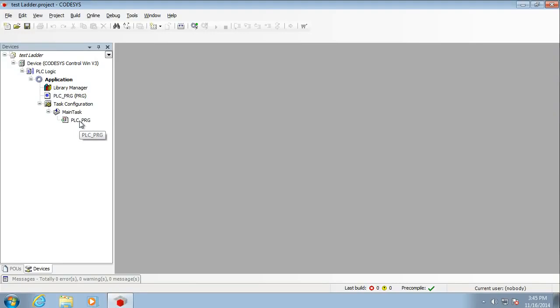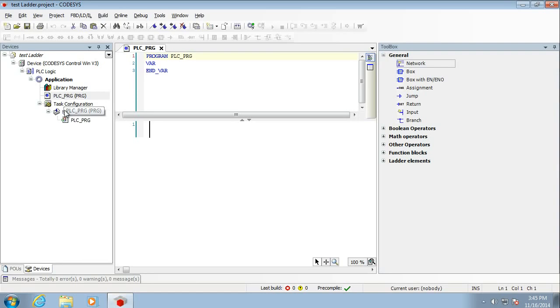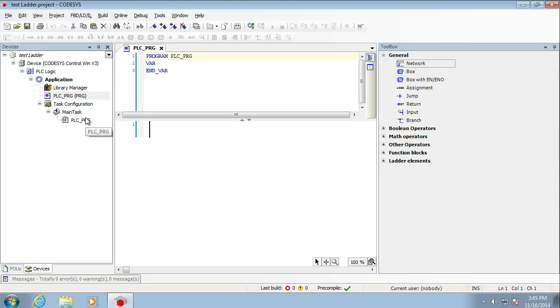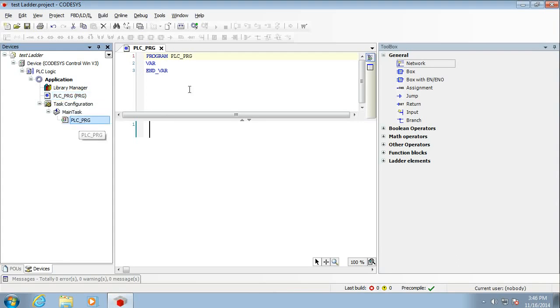Very similar to how we're just going to generate a variable here. So as per IEC 61131, we've got our PLC program file up here. Now you'll also note down here under the main task, it's referenced so that it's being run. This is if anyone's ever used jumps files in the old Allen Bradley days, then this is the equivalent down here under the main task. This is telling us that this program organizational unit up here, PLC program in ladder, is down here for being run.